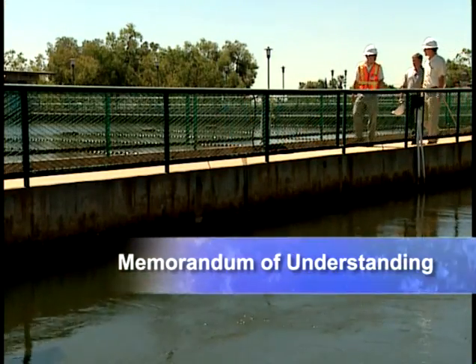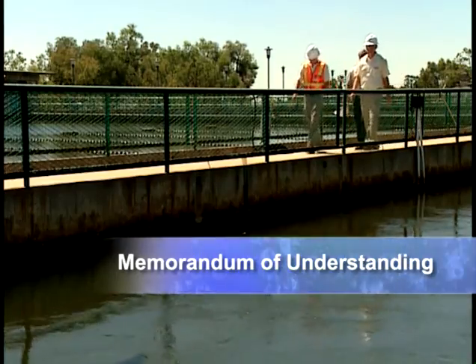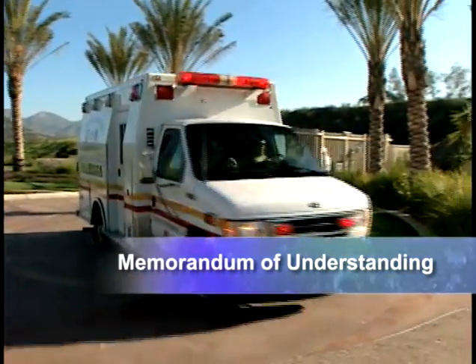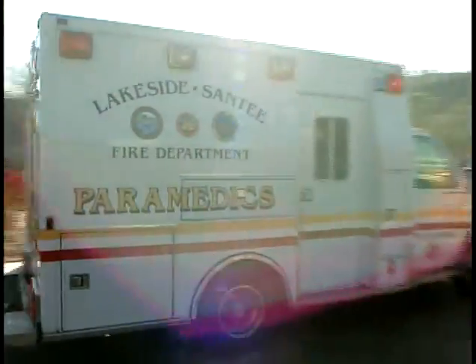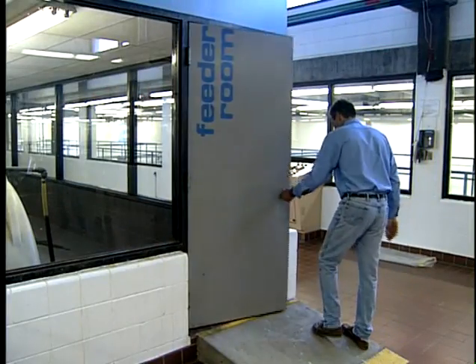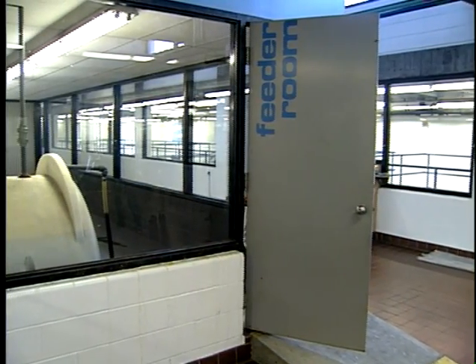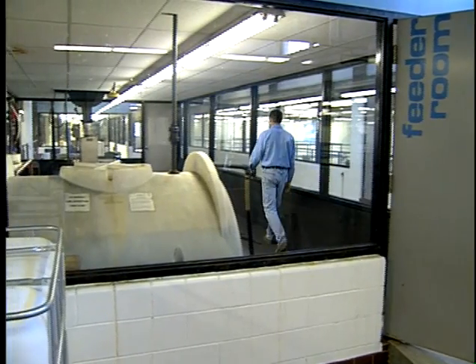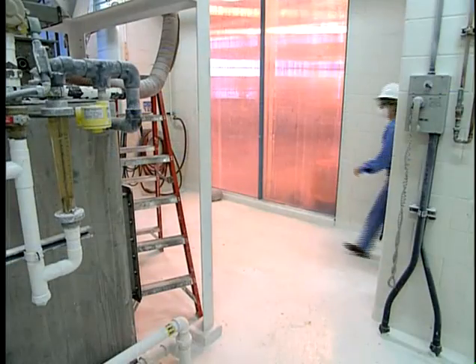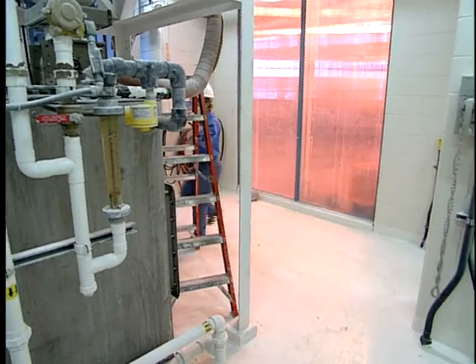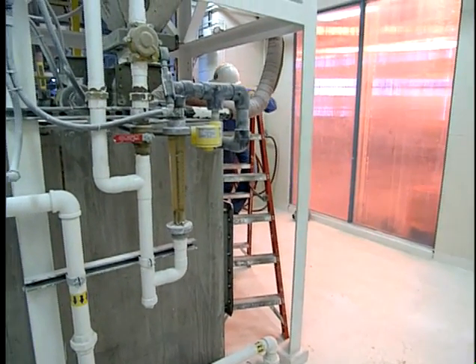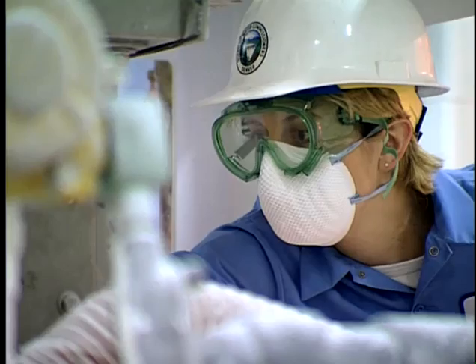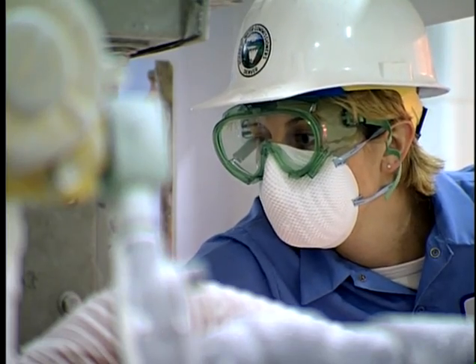A memorandum of understanding should be developed with local emergency responders that outlines the planned and coordinated response to incidents. The OSHA PSM standard calls for the development and implementation of written operating procedures for the chemical processes, including procedures for each operating phase, operating limitations, and safety and health considerations.